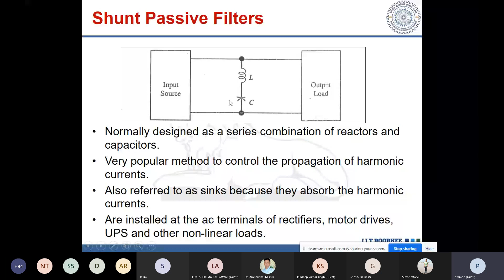It can import harmonics from other nonlinear loads. Because this is an LC tuned filter, when it is connected into the system, the current will not come only from the load. Current may come from the source end also. Source end means other nonlinear loads connected to the network, and those nonlinear loads also inject harmonic current. So rather than going somewhere else, that current may be absorbed by the filter. So it imports harmonics from the other nonlinear loads.